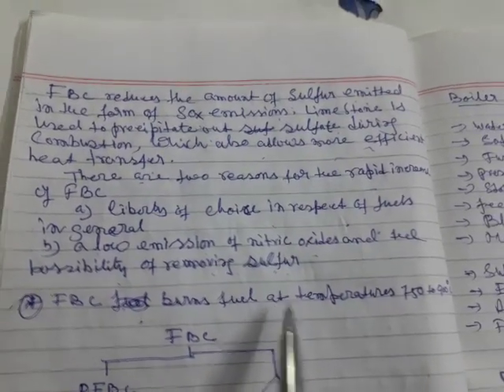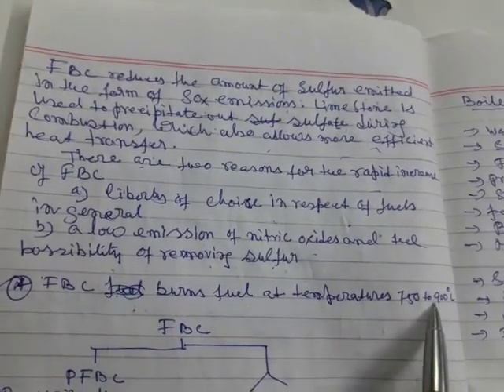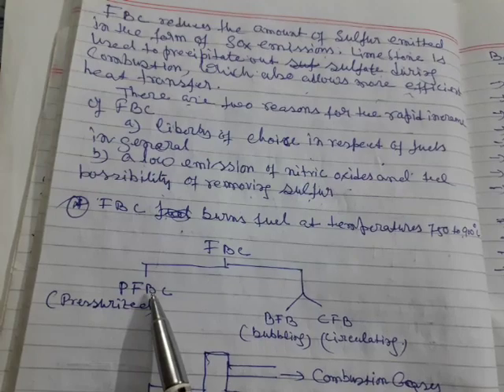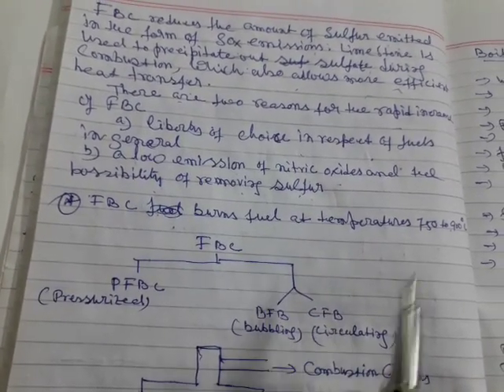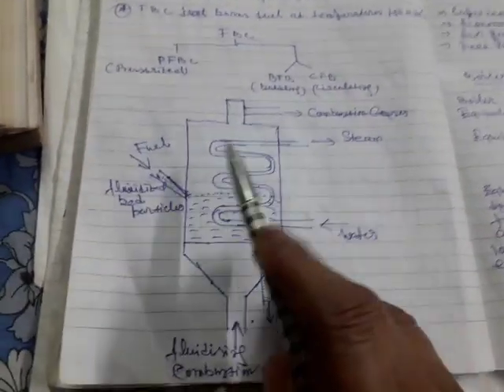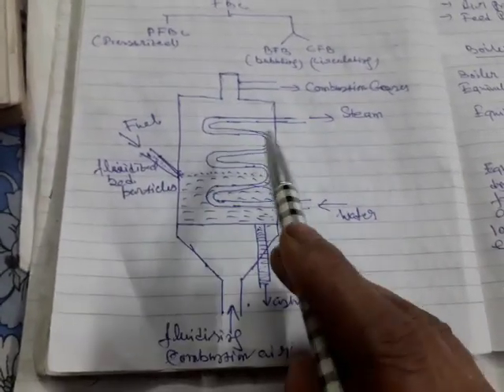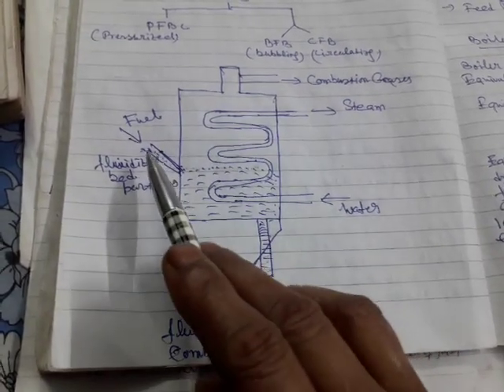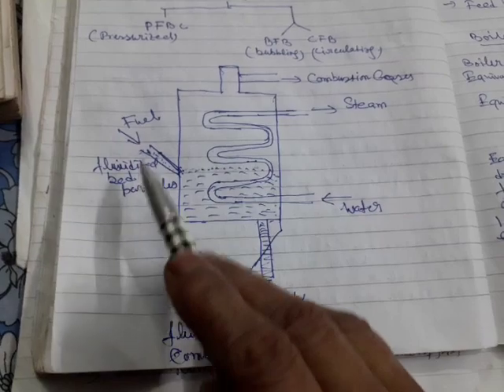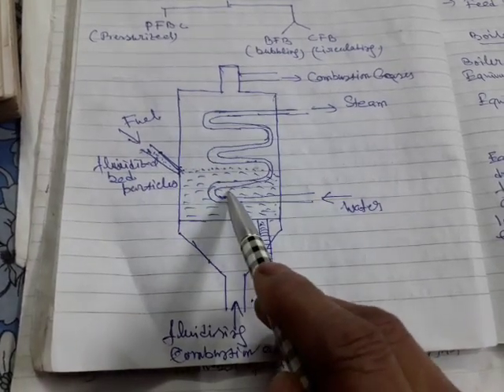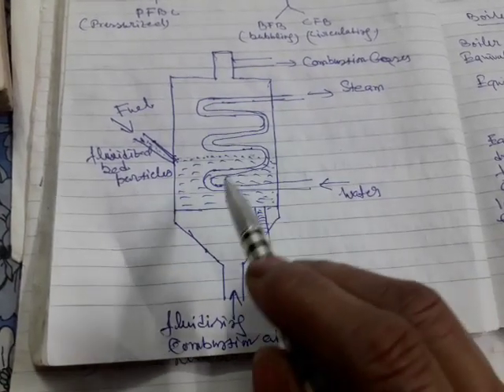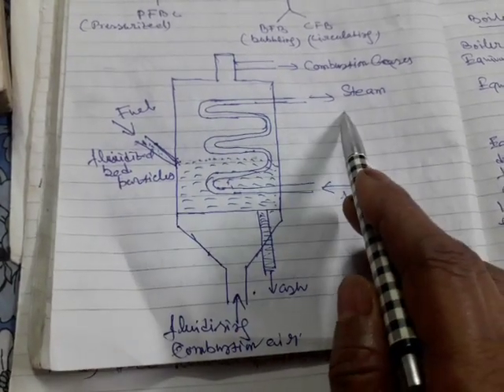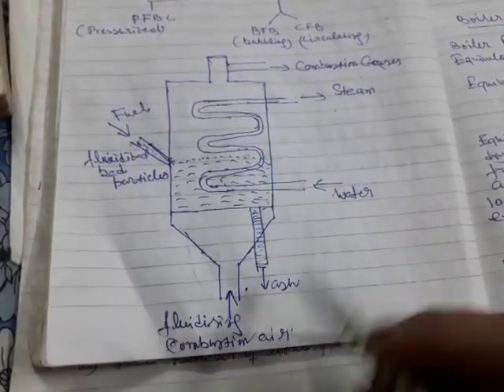FBC burns fuel at approximately 750 to 900 degrees Celsius. There are two types of FBC: pressurized fluidized bed combustion and bubbling or circulating fluidized bed. In the simple diagram, fuel particles enter the combustion chamber along with fluidized combustion air, water enters the tube and steam comes out, and combustion gases exit.